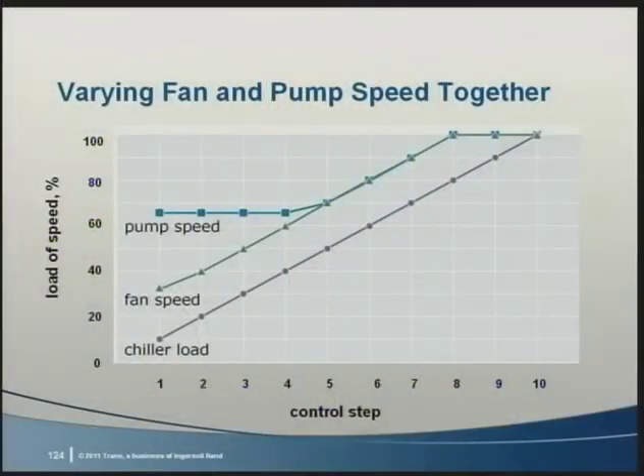The control strategy at Winchester Medical Center is, until the chiller gets below 80% load, as measured by flow rate and temperature difference, operate the condenser water pump and tower fan at the design speed. This keeps the chiller out of surge and allows the system to operate efficiently. Below 80% chiller load, operate the pump and tower speeds to be 20% plus the chiller load.